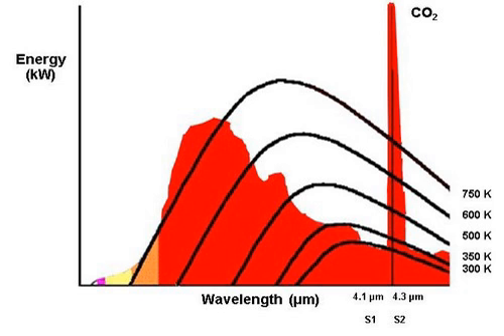The cause is similar to what a firefighter does if he approaches a hot fire. He protects himself by means of a water vapor screen against the enormous infrared heat radiation. The presence of water vapor, fog, or light rain will then also protect the monitor, causing it to not see the fire. Visible light will, however, be transmitted through the water vapor screen, as can easily be seen by the fact that a human can still see the flames through the water vapor screen. The usual response time of an IR detector is 3 to 5 seconds.